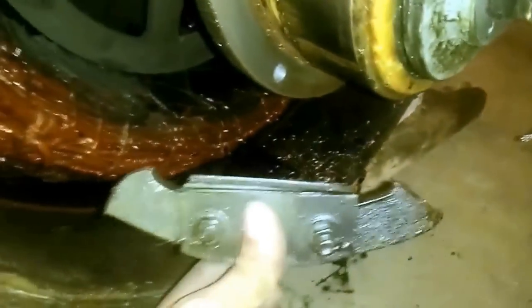The cover on the drive side inside. One of the primary reasons for the entire winding failure, you can see the winding blown out on the other side, is because this part, which is meant for dynamic balancing and is supposed to be located here, broke and hit the winding. You can see it's totally blown up there. That's the state of this winding right now.